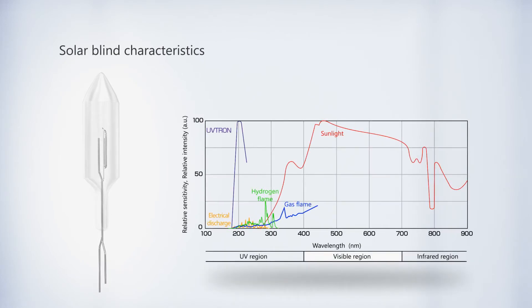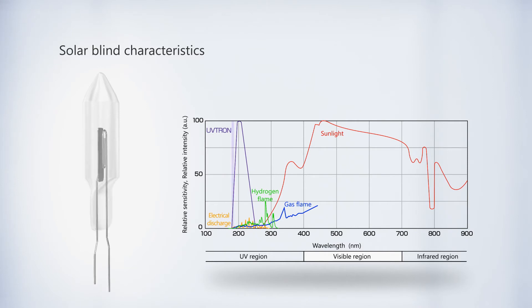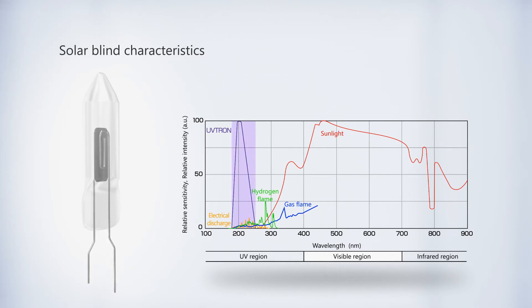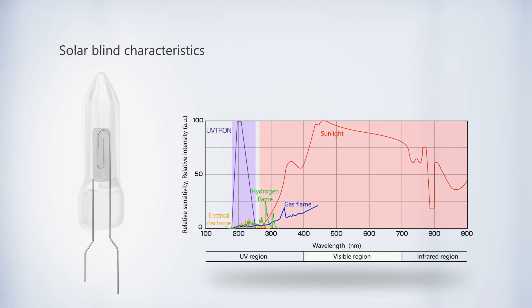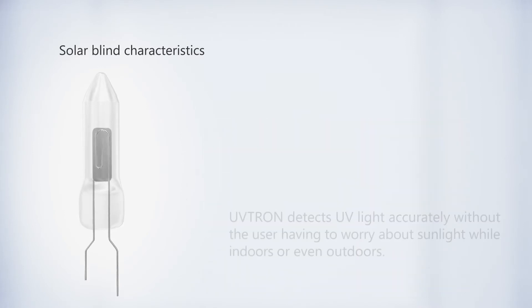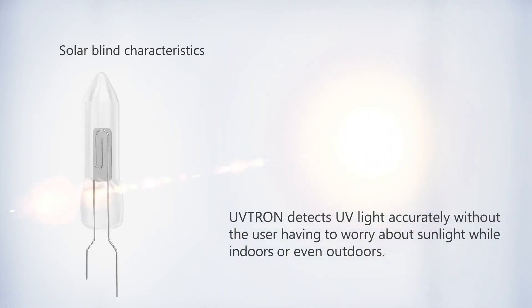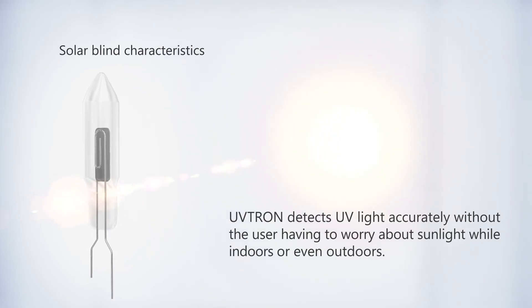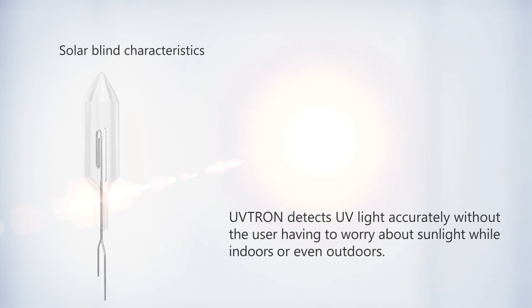UVtron has sensitivity in a very narrow spectral range from 185 to 260 nanometers. It exhibits so-called solar blind characteristics and so is unaffected by sunlight. This enables UVtron to detect UV light accurately without caring about sunlight, whether indoors or even outdoors.